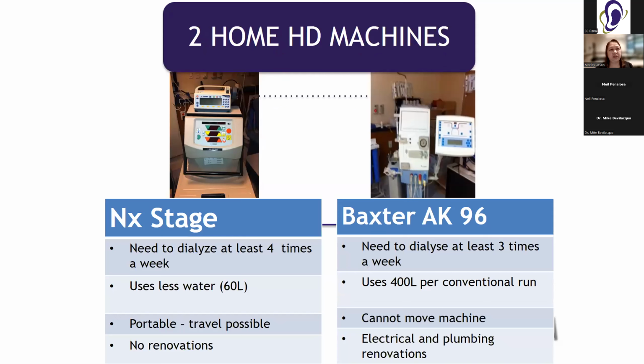So these are the two different machines that you could choose from with the guidance from a nephrologist and the home hemo team. The two machines are quite different. They differ in efficiency. The machine on your left of the screen is called the NxStage. You need to do more dialysis on this machine, as it requires the patient to dialyze a minimum of 4 times a week for at least 5 hours at a time, and it uses significantly less water at about 60 liters per treatment. While the machine on your right is the AK machine, and it requires at least 3 times a week for at least 4 hours, and it can use about 400 liters of water per treatment.